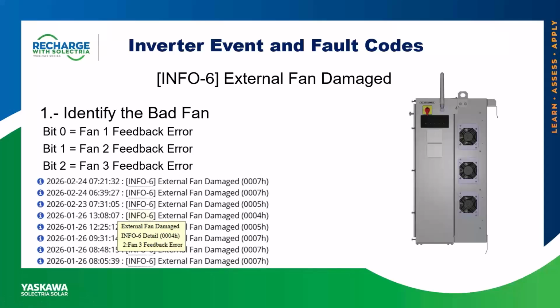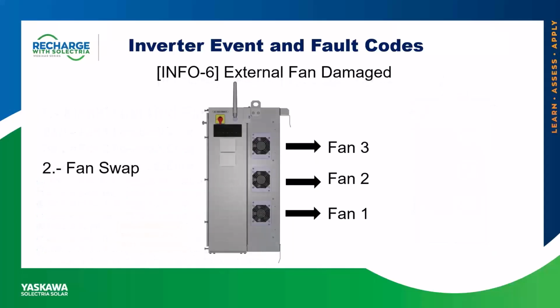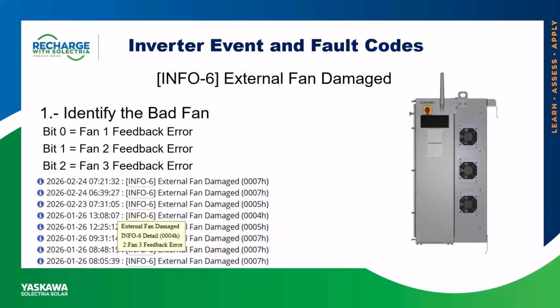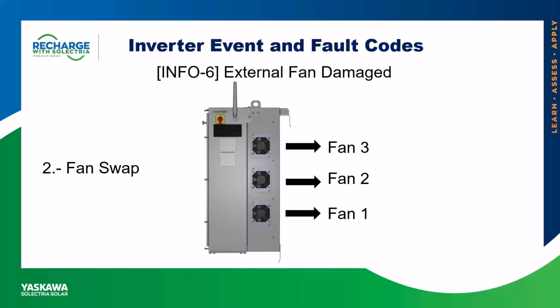Now, if you get a bit 0, it's going to be fan 1; bit 1, fan 2 feedback error; and a bit 2 is going to be fan 3 feedback error, as the picture shows. Now, you may think, well, the top fan is fan number 1. It is not. It's fan number 3, the middle is fan number 2, and the bottom is fan number 1. So now that we've identified, going back to the previous slide, that fan number 3 is the one that has failed, we go to our top fan, and what's recommended is a fan swap.